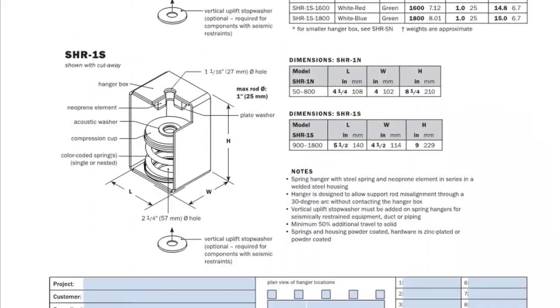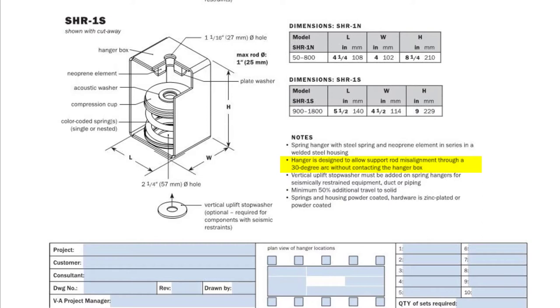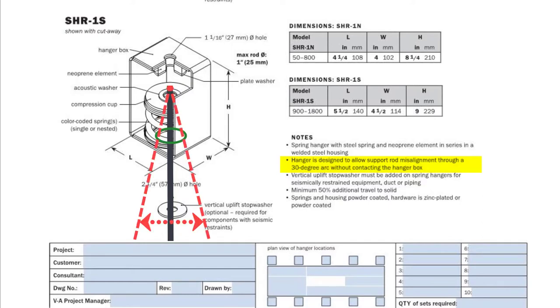One of the notes on most of the spring hanger data sheets states that the hanger is designed to allow support rod misalignment through a 30 degree arc without contacting the hanger box. So while it is best for both the upper and lower hanger rods to be vertical, collinear, and parallel with the box housing, it is common for one or the other to be at a slight angle to the box. This design feature allows a hanger rod to pass through the hole in the bottom of the hanger box and be 15 degrees off vertical in any direction before the rod makes contact. This is a common feature that is often specified to help avoid short-circuiting.